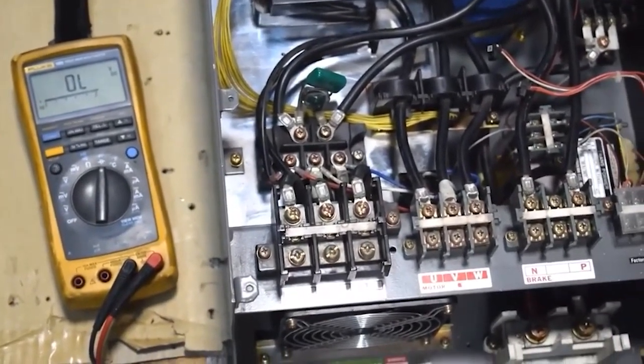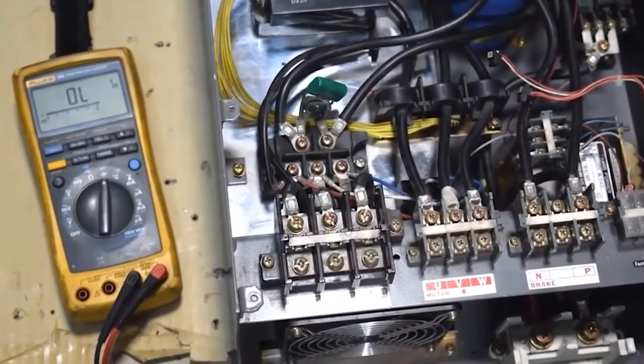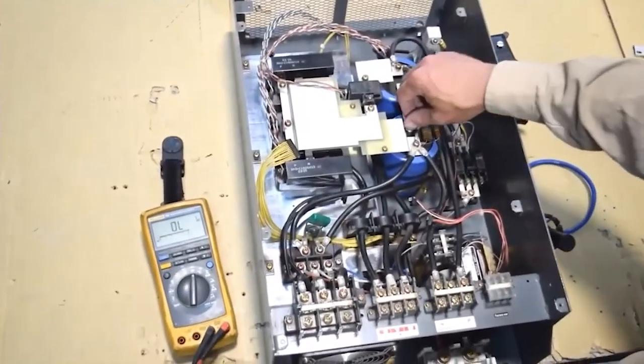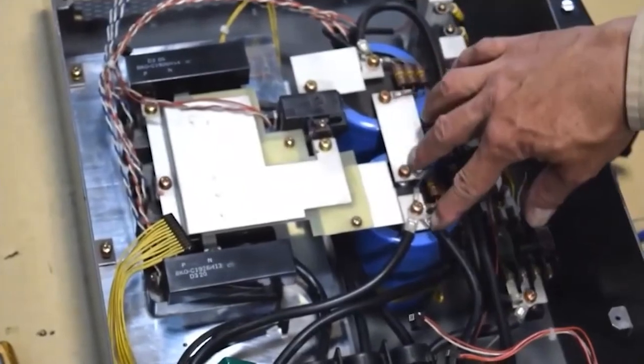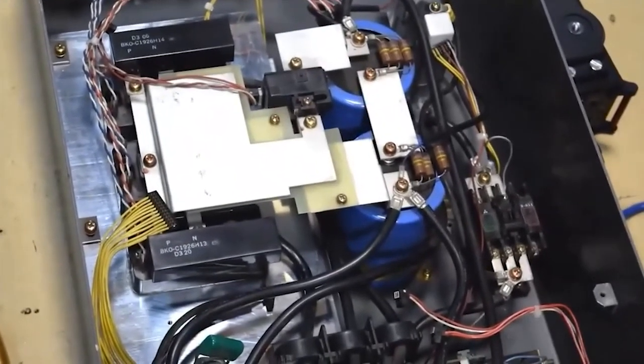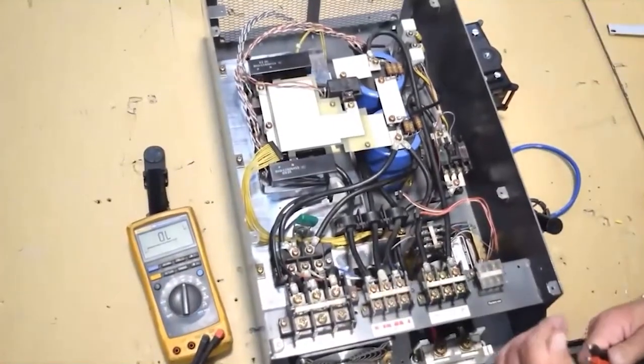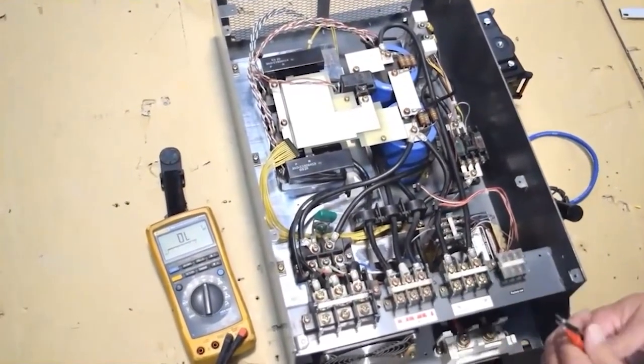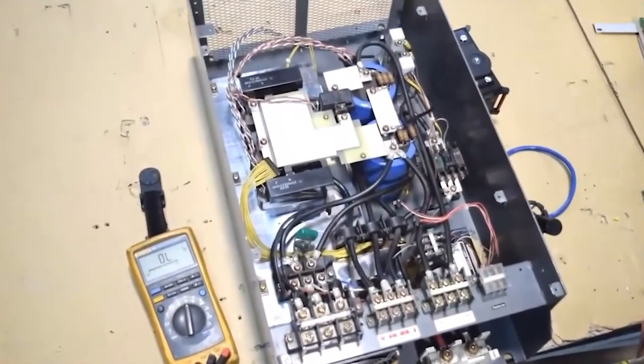So then I do the same thing where I put my positive lead on my positive bus and I measure all my inputs and outputs again. And it just lets me know that there's a problem if I can't charge. It's also an indicator that your capacitors are charging properly. If you've got a bad capacitor in it, it won't charge.